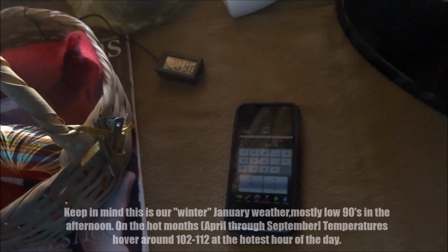It's in that range. It's 9 a.m. so seems to be running pretty good. Temperature split is exactly 20 degrees Fahrenheit. We've got a 66 degree intake and a 46 degree supply, so it's working just as expected. If we turn down the fan speed to low, it actually drops it way more. So it's running pretty good.